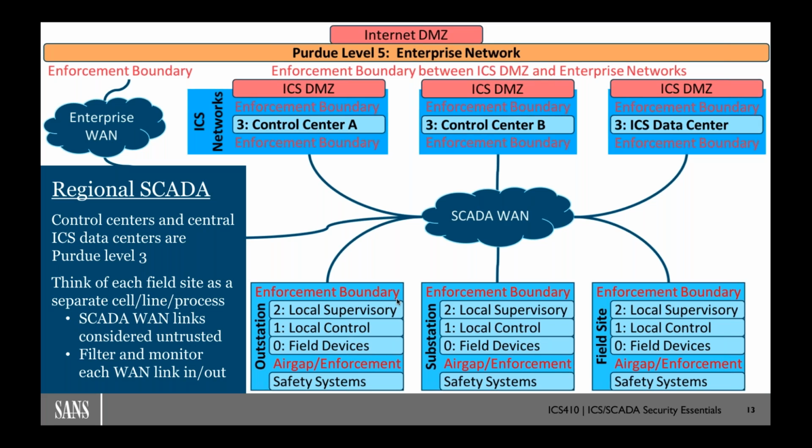Yes, bad idea. We don't want any type of SIEM traffic being pushed outside of that control environment, especially through the public internet to mobile devices, right? We should definitely remember this is a highly secure environment. Just ask your business what happens if you lose one of the plants, and you definitely don't want to be the one that created the bus lane for the attackers to drive their explosives into your virtual plant through these virtual links. So yeah, I definitely would not do that.